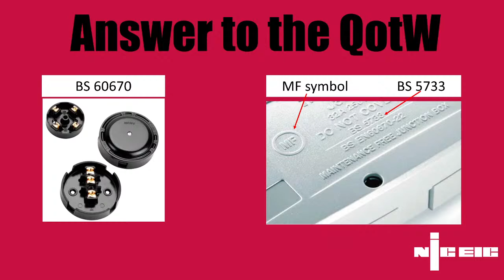This example does actually reference the standard as well, BS 5733, and it also says in text that it's a maintenance-free connection. So they've sort of gone triple-wise there, but you only have to have that MF. If you are in doubt whether or not an electrical connection you're looking to make needs to be accessible in the future, always refer to the manufacturer's instructions. If you're ever in doubt, they will always be the ones to give you the answer. It's their product. Our regs state to take account of the manufacturer's instructions, so you're doing everything right.